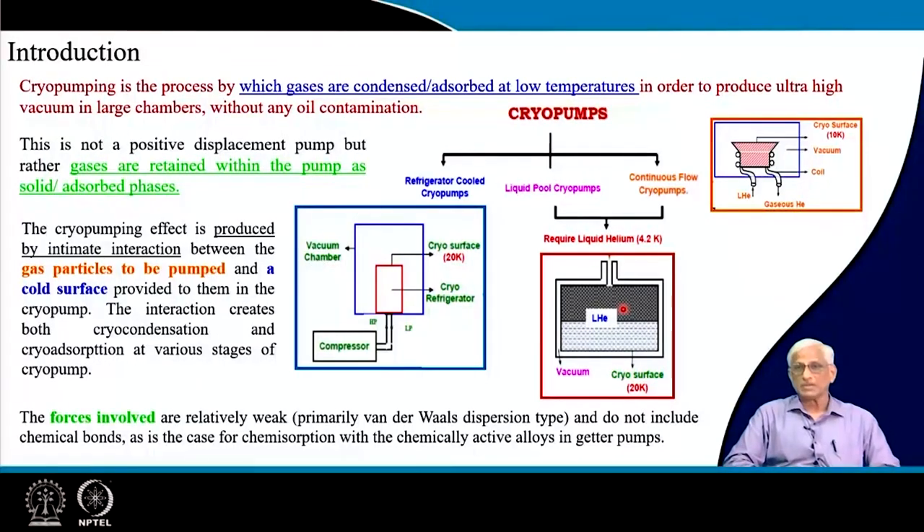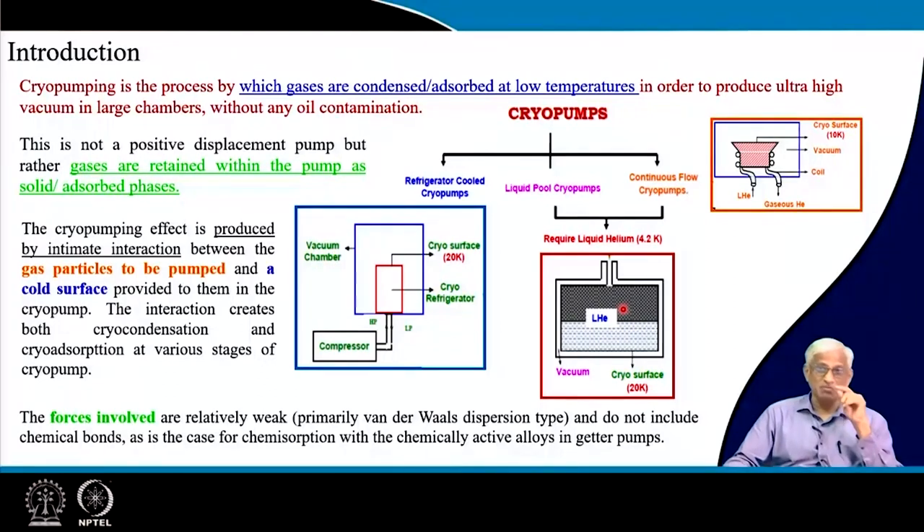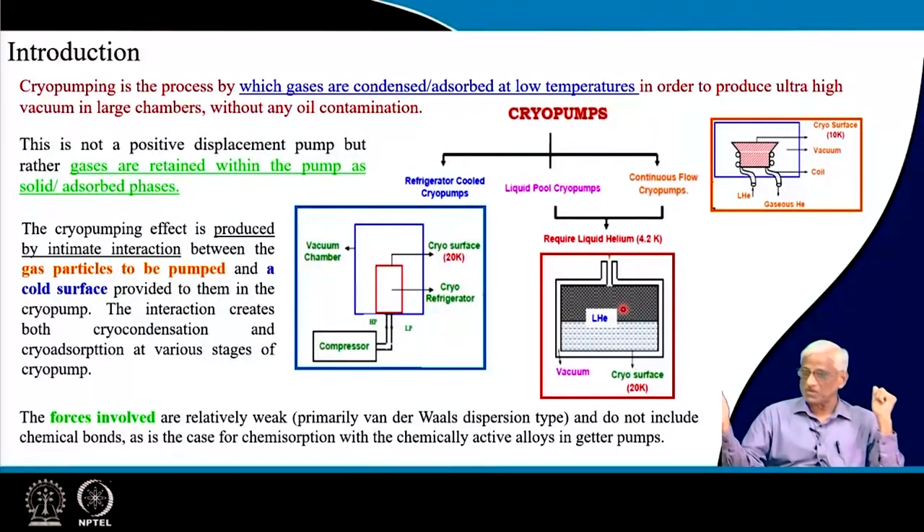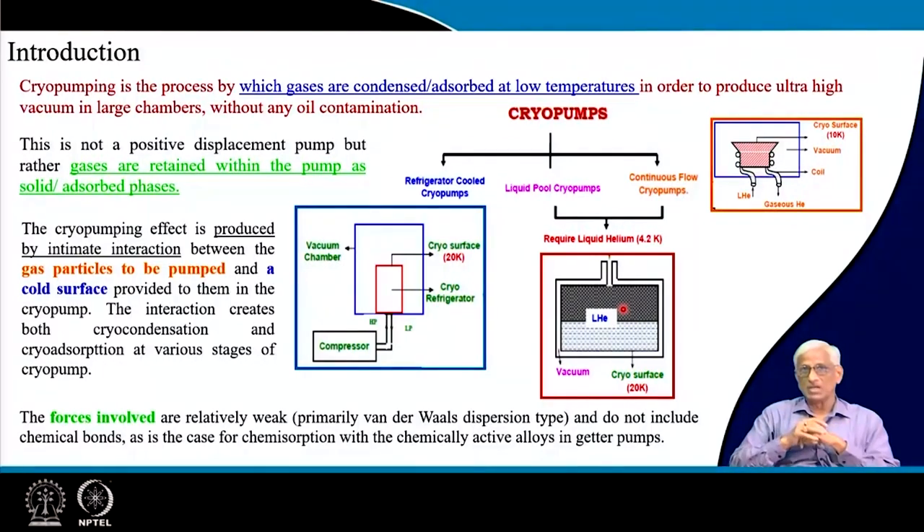What is cryo pumping? So far in earlier pumps we have seen positive displacement pumps like rotary and turbo molecular pumps. We have also seen adsorption or getter pumps where molecules are not taken out of the chamber but are trapped by surfaces — physisorption or chemisorption. In cryo pumps, surface pumping is the only process used: there is a condenser inside the vacuum chamber which is cooled to cryogenic temperatures — minus 196 degrees with liquid nitrogen or minus 269 degrees with liquid helium.